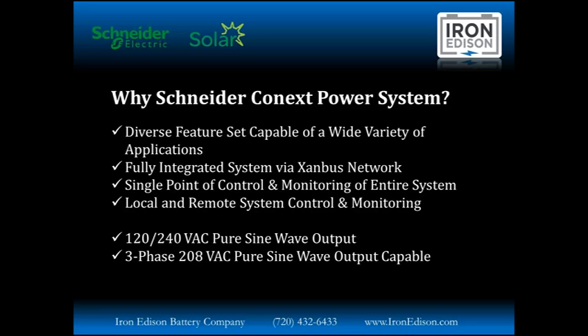In addition, the Schneider Electric inverters deliver right out of the box 120/240 volt power, pure sine wave output. It's super clean power. And the inverters can also be configured for 3-phase 208 volt AC applications. That's what we use here in the shop. A lot of other businesses use 3-phase, or even large residences may use 3-phase 208. So it's a very simple change to adjust or adapt these inverters to meet each specific application.